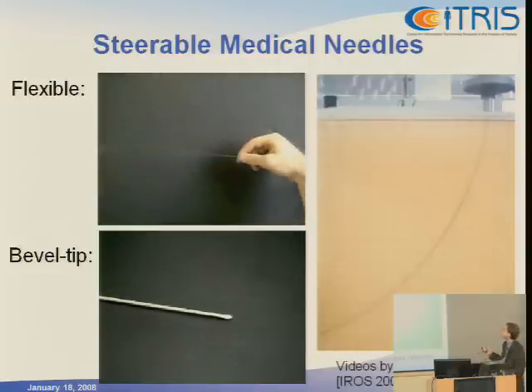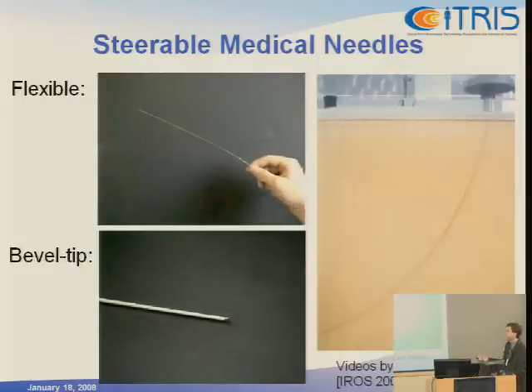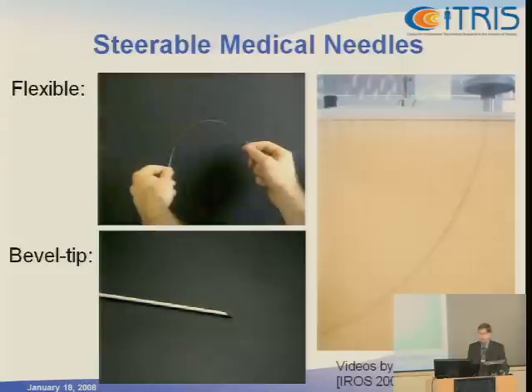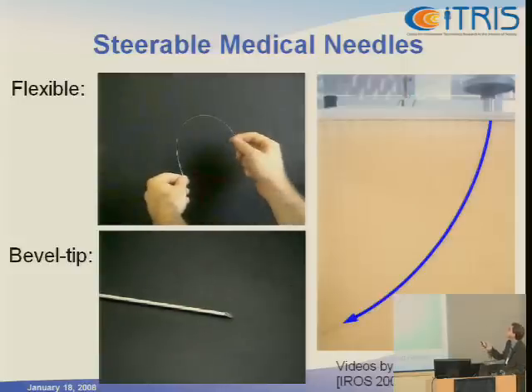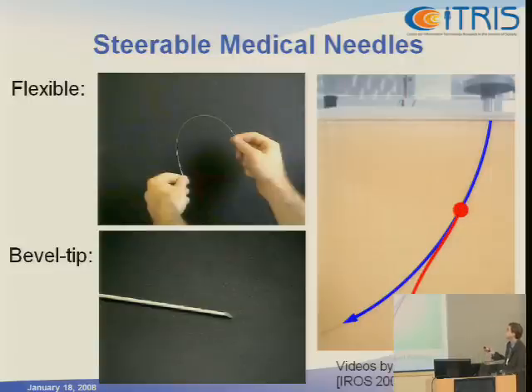We can see in the image on the right that when this needle was inserted into an artificial tissue phantom, it followed this curved path — I can highlight the path there in blue. If we instead decide to insert the needle and then at some point rotate the base by 180 degrees, because the needles are torsionally stiff even though they're flexible, this will change the direction that the bevel points, and we can follow a path with a curve radius of curvature in the opposite direction.